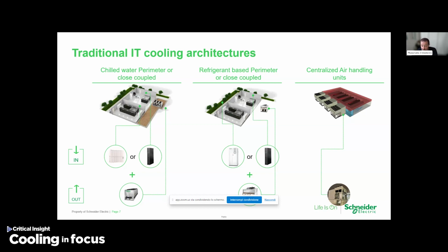This trend aligns with densification, but also with two other things. First, removing the refrigerant from the equation, or from the white space. Refrigerant-based systems or centralized air handling units have contact between the white space air and the refrigerant, and unfortunately the new refrigerants are slightly flammable.